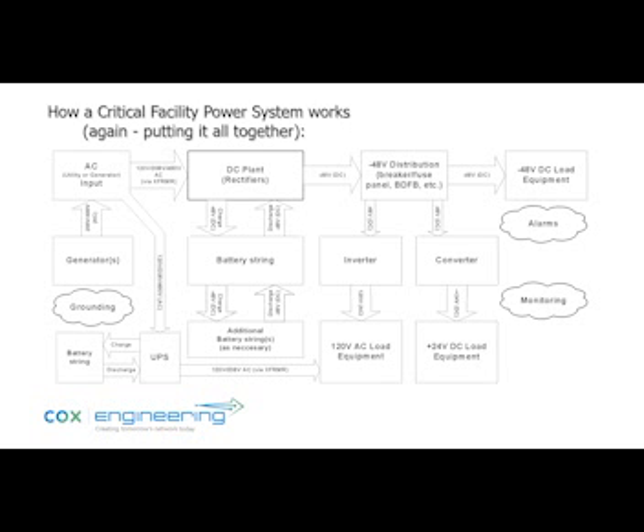So we're putting this all together, and now you should be able to look at this drawing and have a pretty good idea about what's going on here. The AC power comes in, it may come from the generator if the utility power is gone, but it goes into the DC plant, and there are battery strings involved. There's a UPS and battery string potentially, which then powers the AC equipment. The AC equipment can also be powered from an inverter that's hanging off of the DC plant.